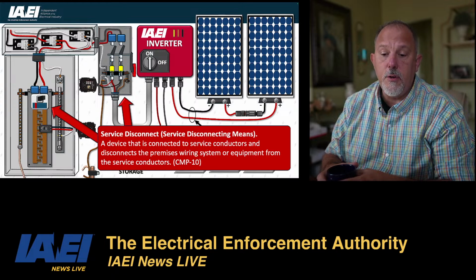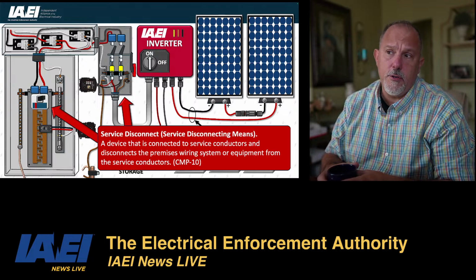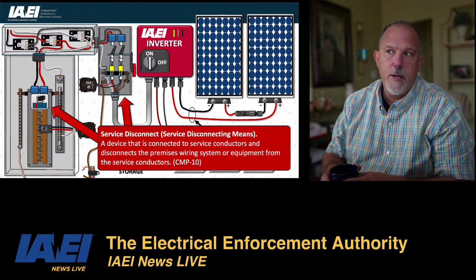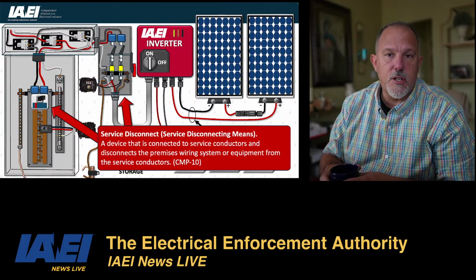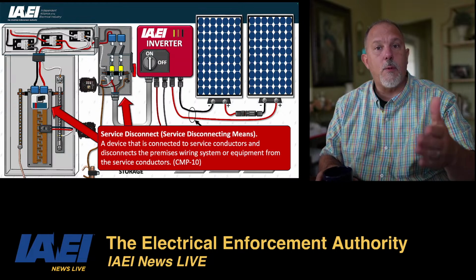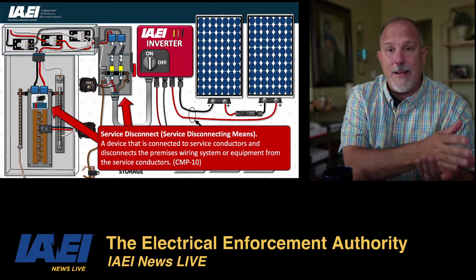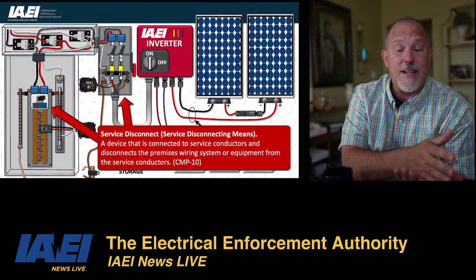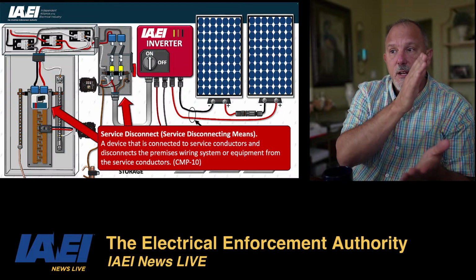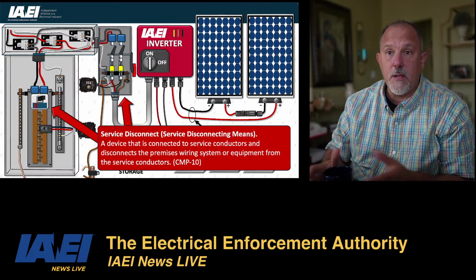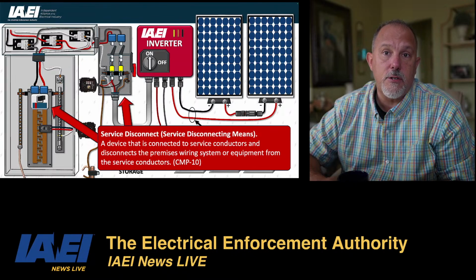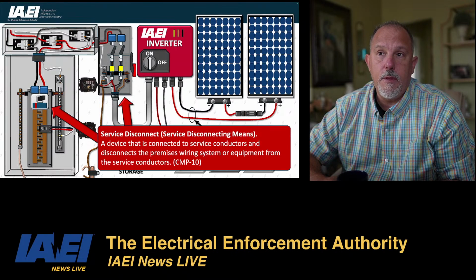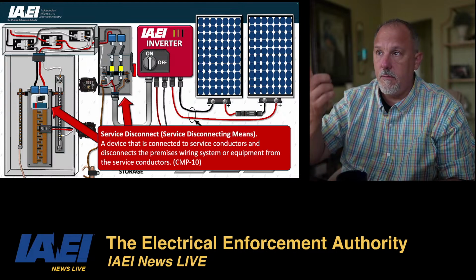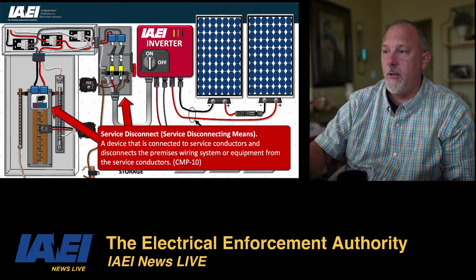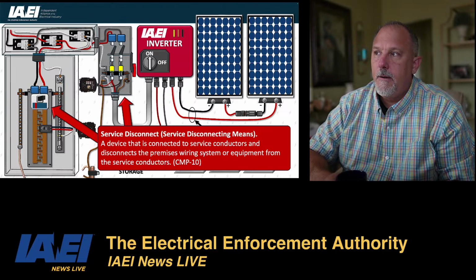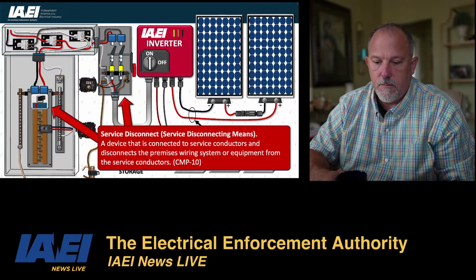Yeah, and the meter. Your service point may be the meter, right, Andrew? That may be the service point, and that's why the utility will tell you they don't want the grounding and bonding done in that meter. It's ahead of the service disconnecting means. But those conductors that come from that meter down are typically under the purview of the National Electrical Code. The utility does not own the panel board, right? I'm not showing the meter in this case, but that service point is your line of demarcation.